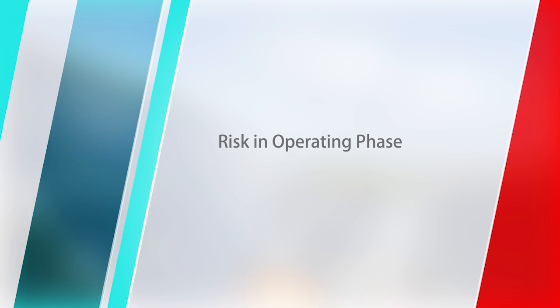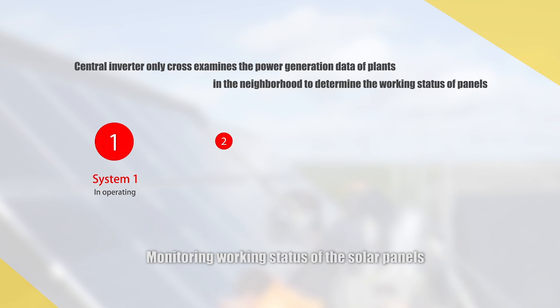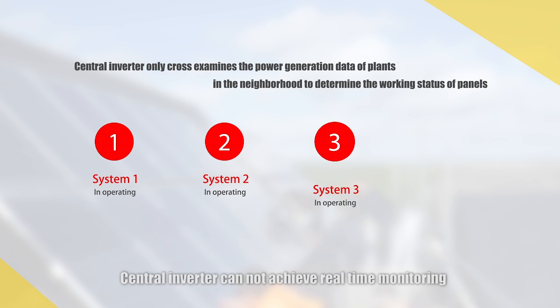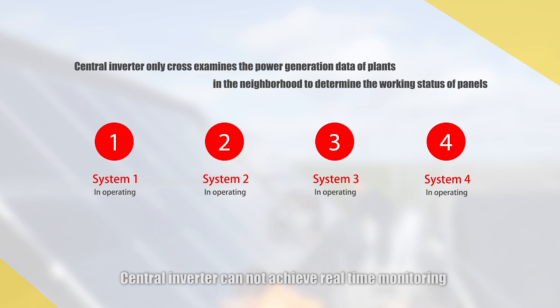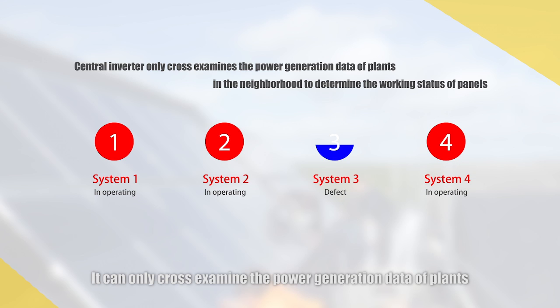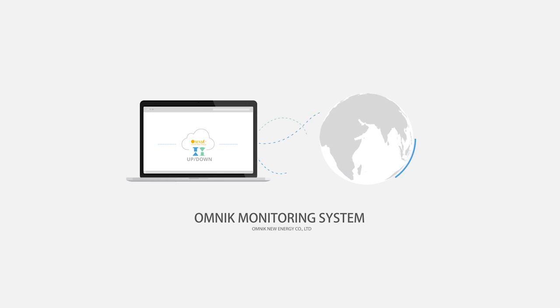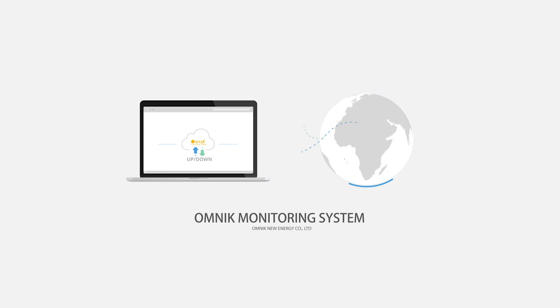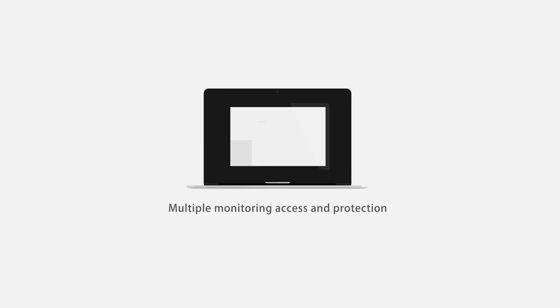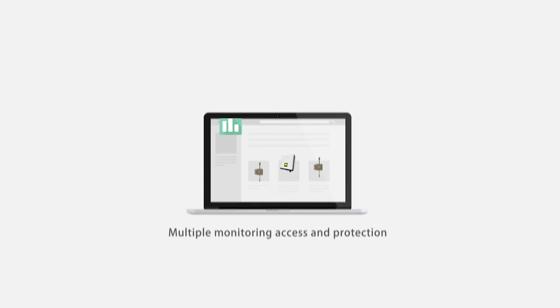Regarding risk in the operating phase and monitoring of working status: central inverters cannot achieve real-time monitoring — they can only cross-examine the power generation data of neighboring plants to determine the working status of panels. Each string inverter can detect malfunction, narrowing the scope of defective panels down to dozens. Micro inverters can even monitor each individual panel.